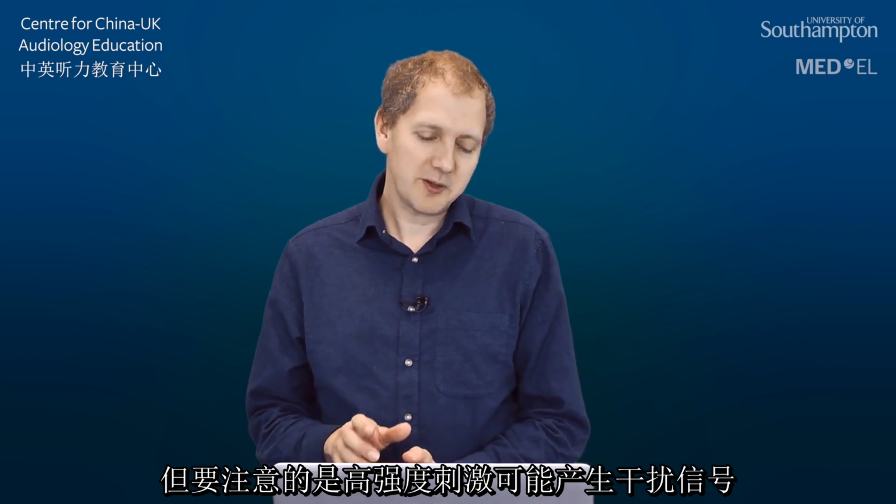Steady state responses can go a bit louder than brainstem responses, although an issue to be aware of is there may be artifacts at very high levels with steady state responses. There's a possible issue of vestibular artifact when we get to very, very high stimulus levels. So maybe just something to be aware of.